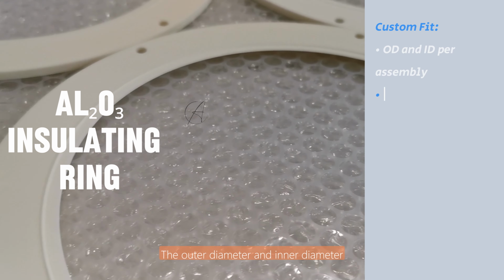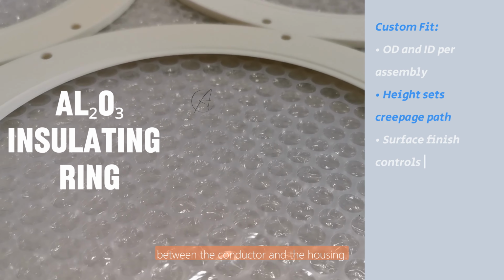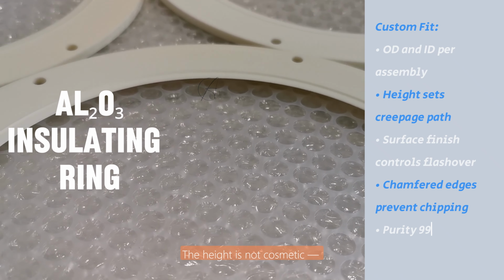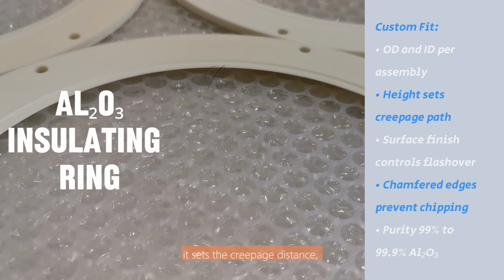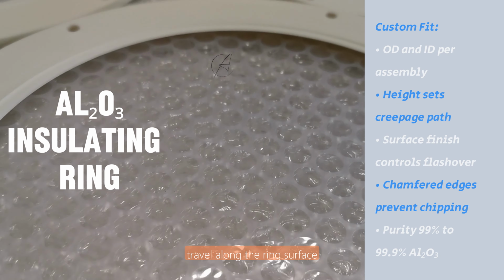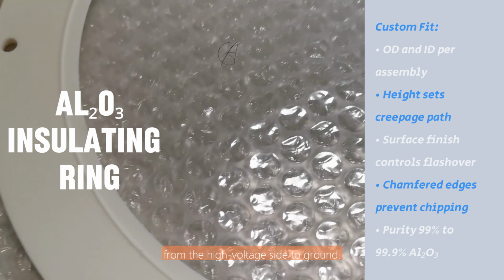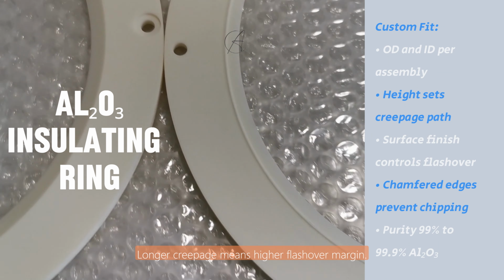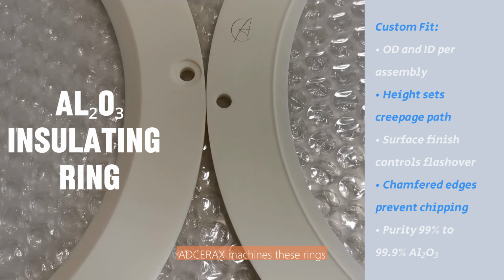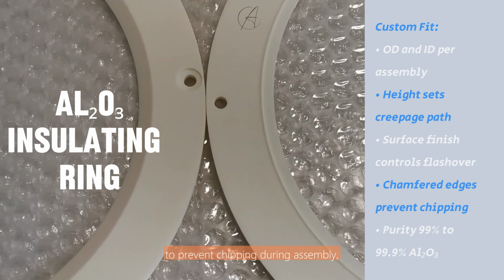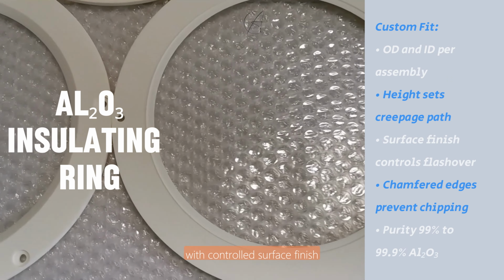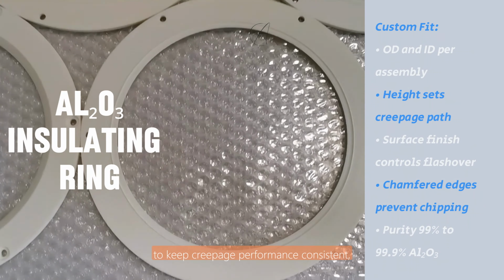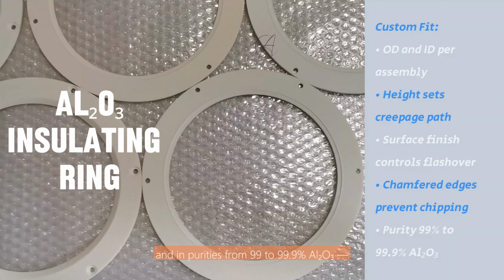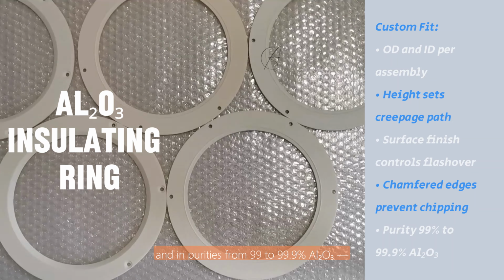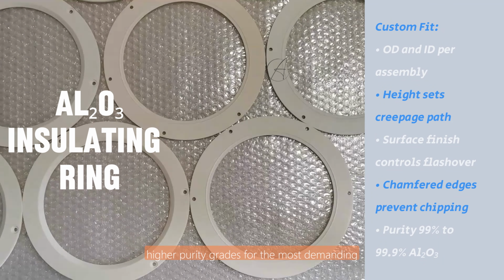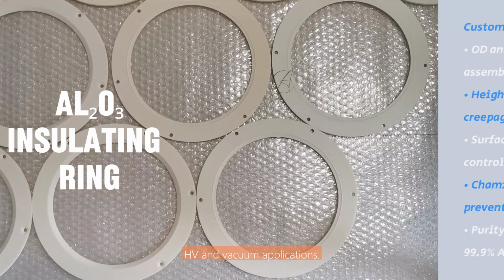The outer diameter and inner diameter set how the ring fits between the conductor and the housing. The height is not cosmetic, it sets the creepage distance, the length that an electrical arc would have to travel along the ring surface from the high voltage side to ground. Longer creepage means higher flashover margin. ADCERAX machines these rings with chamfered edges to prevent chipping during assembly, with controlled surface finish to keep creepage performance consistent, and purities from 99 to 99.9% aluminum oxide, higher purity grades for the most demanding HV and vacuum applications.